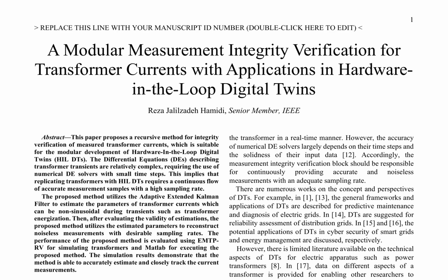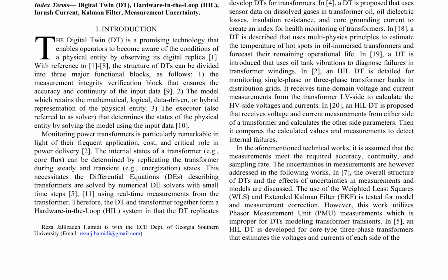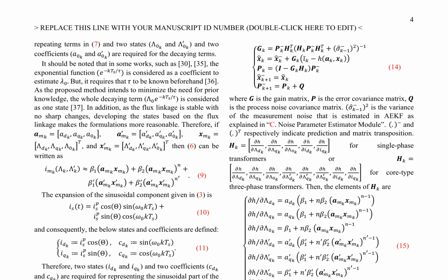The simulation results demonstrate that the method is able to accurately estimate and closely track the current measurements. The proposed method employs a recursive method for integrity verification of measured transformer currents, which is suitable for the modular development of HIL DTs. The differential equations, DE, describing transformer transients are relatively complex, requiring the use of numerical DE solvers with small time steps.